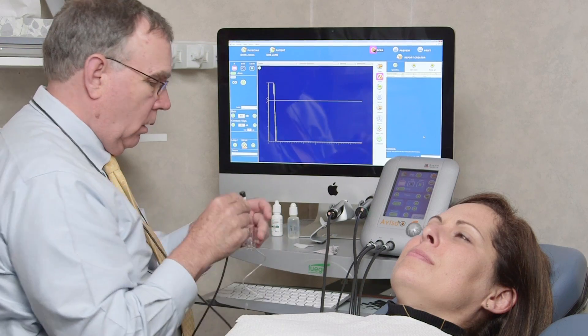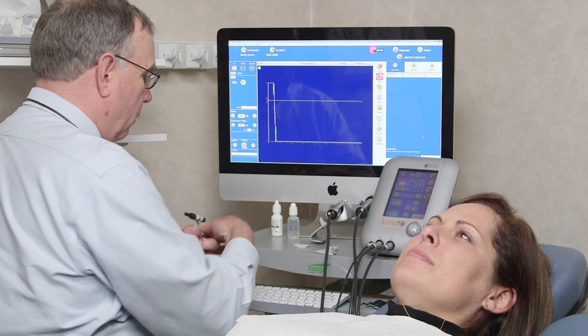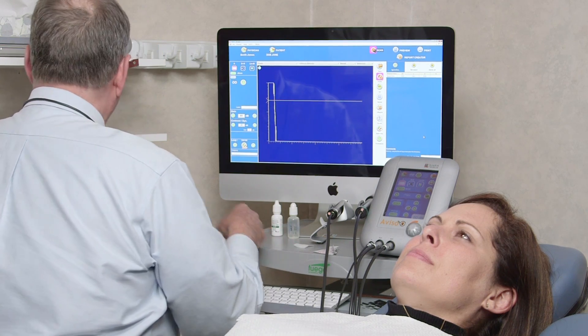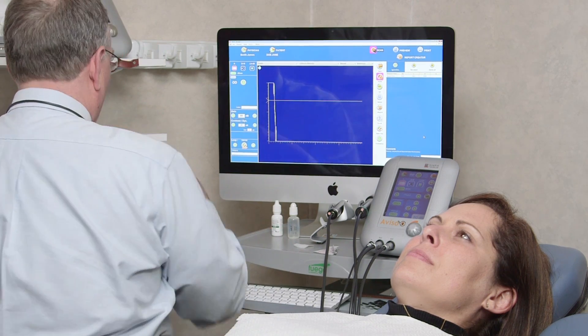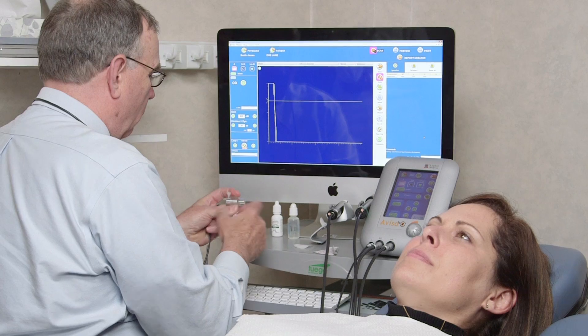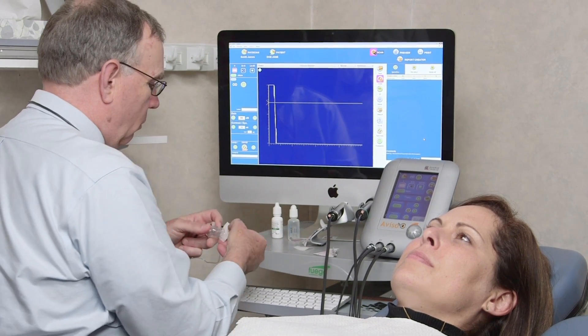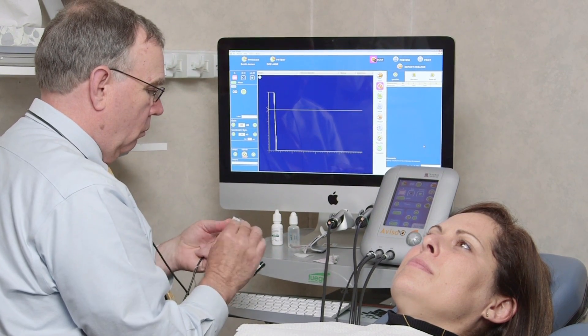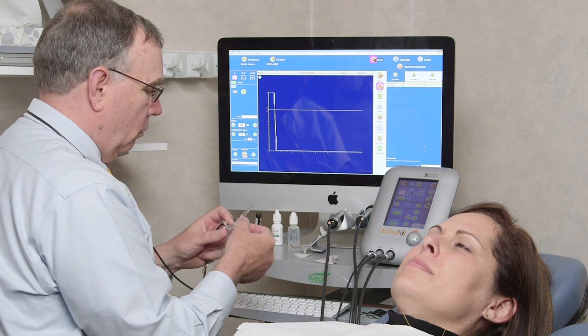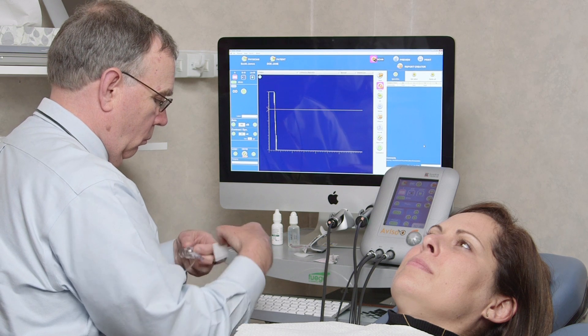Ensure that the correct probe is cleaned and ready to use, and that the rest of the ultrasound device's settings are correct. Check the primary eye to indicate the eye that you will measure first. Remember to always measure both eyes.